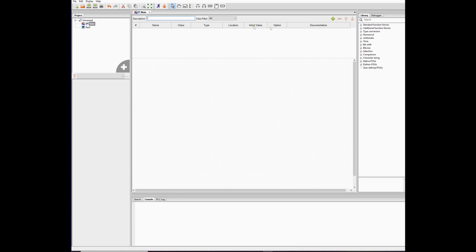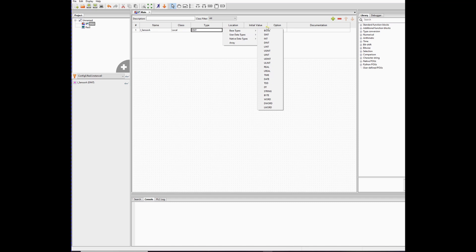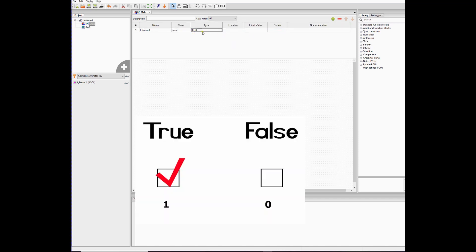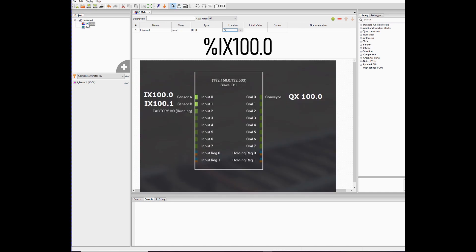Before we program, we need to define our input and output variables. Press plus to add a variable. I'll call it I_sensor_a. The type is base type Bool - Boolean - so it's either one or zero, true or false. The variable I_sensor_a can only have two states: on or off, true or false, zero or one. For the location, press percent, then IX100.0 as the first input.